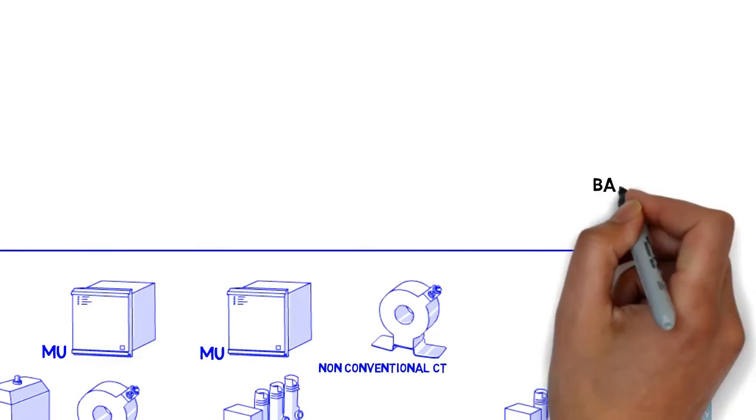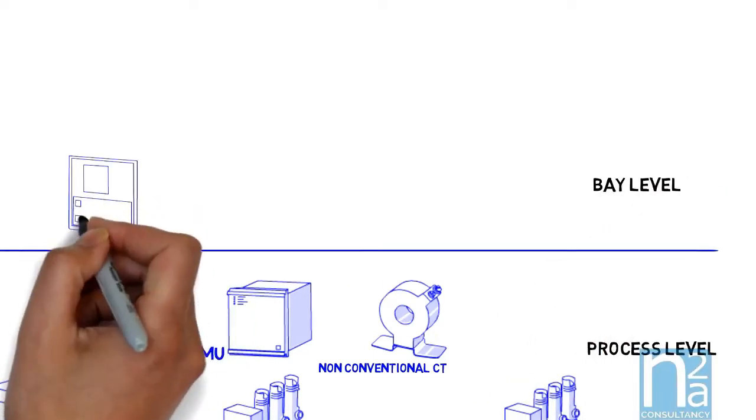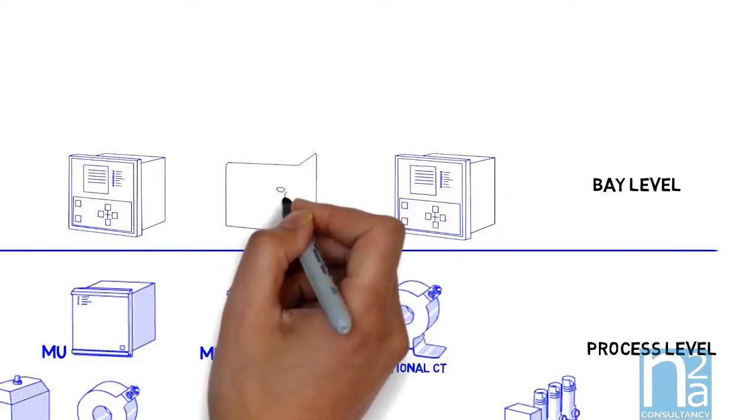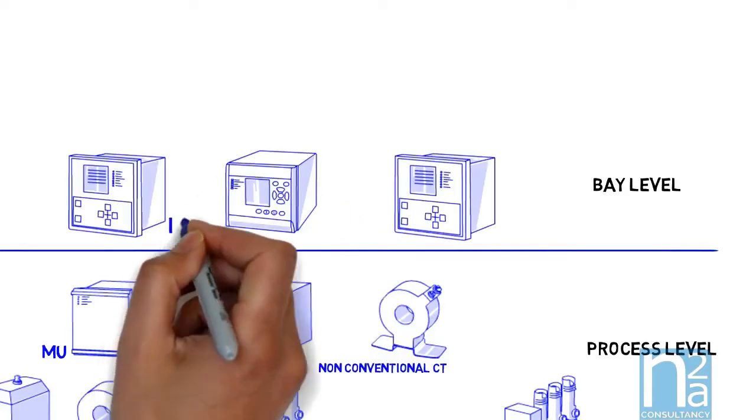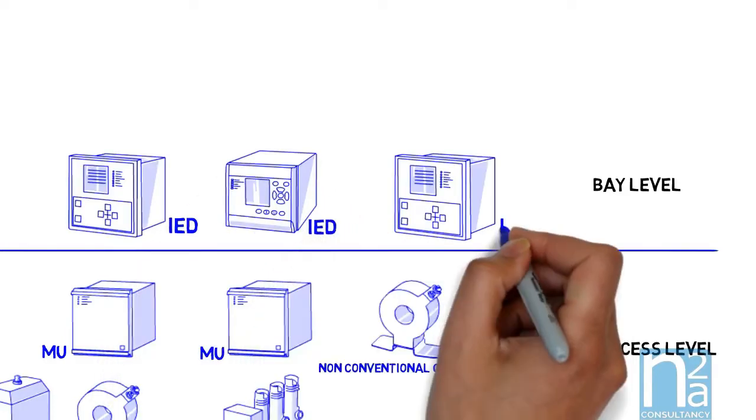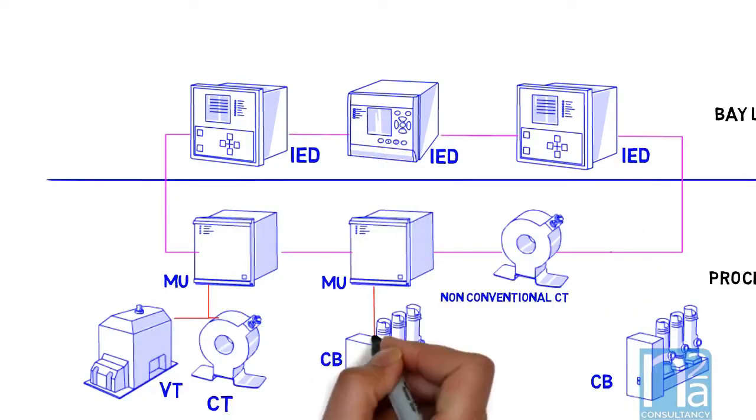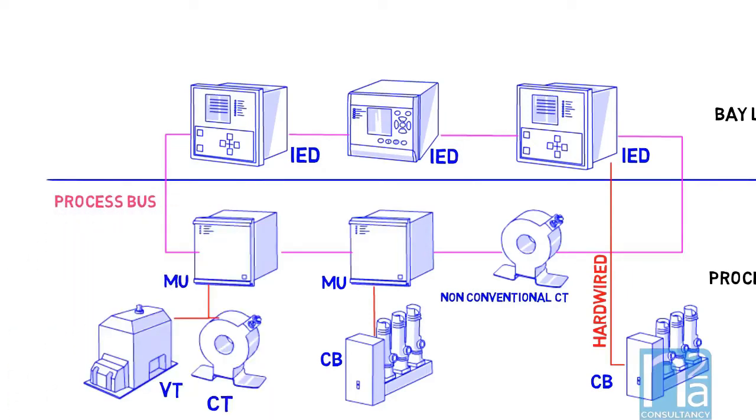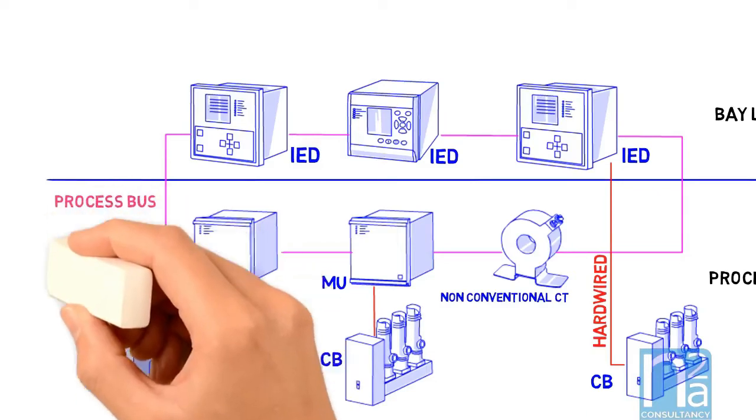The second level is the bay level where we have intelligent electronic devices called IEDs. IEDs is the new name of relays to reflect their capabilities to take decisions based on logic and information collected from the process level devices. IEC 61850 defines process bus to allow communications between IEDs and intelligent instrument and switchgear. Conventional CTs, VTs, and switchgear could also be connected through an analog digital converter called merging unit.